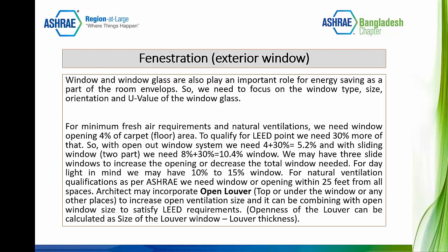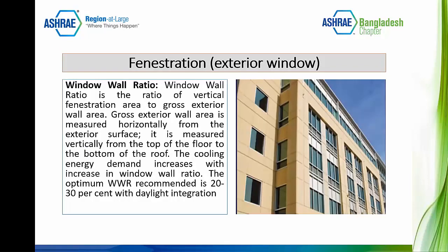Check it out. Then the main culprit of heat gain is called window fenestration. Okay, there's a huge guideline on that. So window-wall ratio is very important in LEED or any building optimization. You have more window, less wall, you have more heat gain, because glass always has a higher U-value than wall. Simple as that. You go to a building and you touch the glass, you will feel the warmth. It means heat is already inside, right?